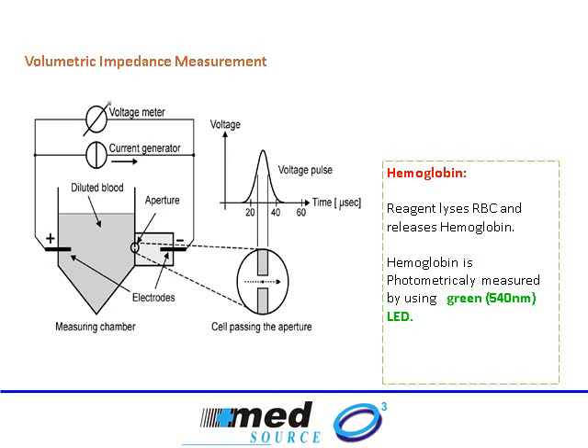One exception is hemoglobin, which is really a protein. Hemoglobin is measured by photometry present inside the analyzer using a green LED. So all the cells are counted on the basis of their size by the cell counter, and hemoglobin is measured photometrically.